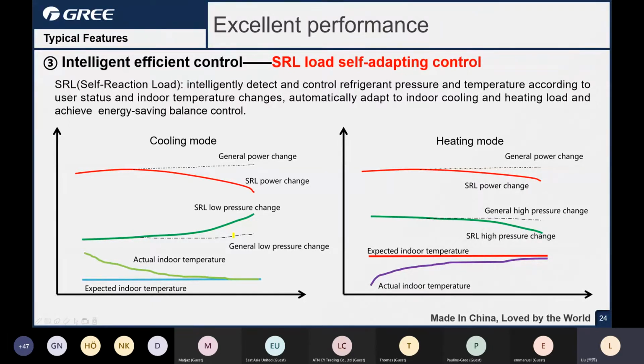Maybe these two look very similar, but SRL, this control logic, makes the units run smarter, because the low pressure change slope is sharper and more responsive than the general one. Okay, and the power change is similar. If the low pressure does not increase, the power consumption will be reduced. So in general, SRL, this control logic, the first advantage is about comfort. That's better for the comfort. Another one is energy saving.